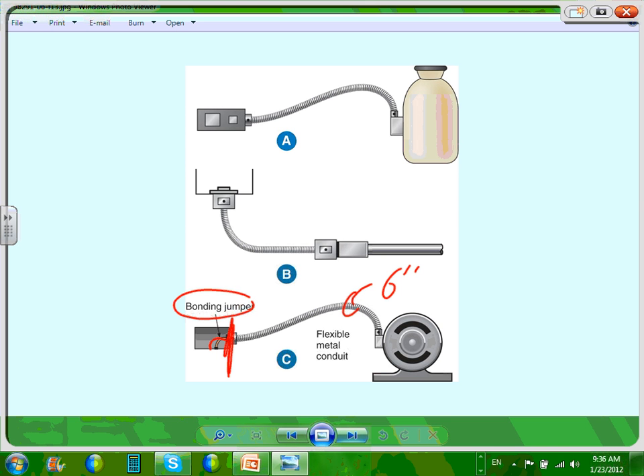So if I can get you to remember, guys, this is flexible metallic conduit, and the second one is liquid tight flexible metallic conduit. Where would we use liquid tight? Wet location. Flexible, dry location. Done. Tie to equipment. Why do we tie to equipment? Ease of installation and absorption of vibration from the system.